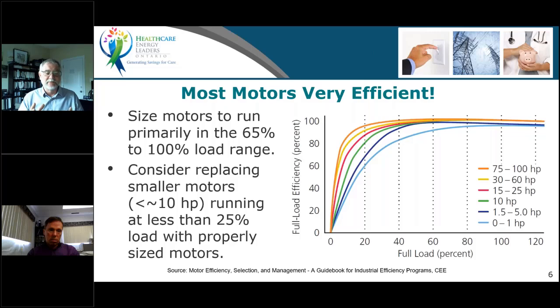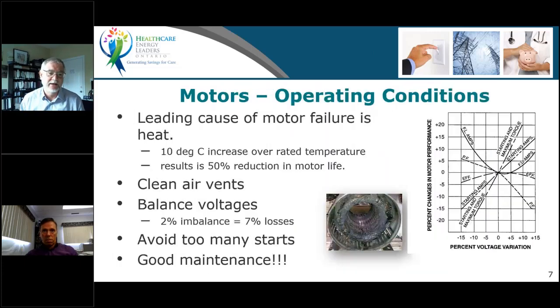So you've got to be really careful looking at it from the motor moving forward. You've got to really go to the load and work your way back up, and then you'll end up in the right situation. Motors do suffer from poor operating conditions, no doubt about it. The number one or leading cause of motor failure is heat from a number of different sources. Keeping them clean, keeping the voltage balanced. If you look on the right-hand side, anything you do to the voltage applied to a motor will reduce its operating efficiency if you move off the nameplate efficiency. Too many starts without a soft start. All of those things lead to a reduction in the motor's life.